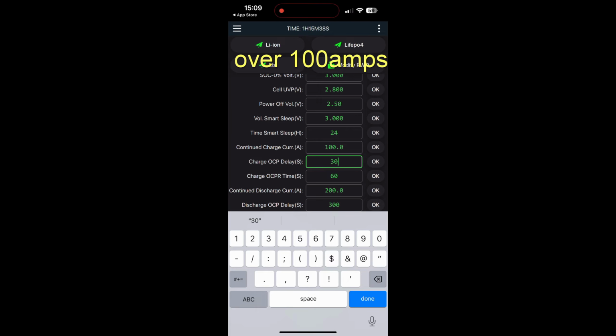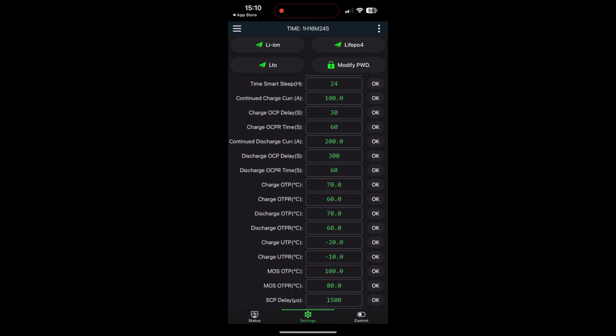Now, these BMSs that we have are a 200 amp BMS with a 350 amp peak. So it will sustain a 100 amp charging current for 30 seconds, and once it's reached 30 seconds, the BMS will disconnect. Now, the setting below that, charge over current protect reset, is how long the BMS will wait until it allows charge current to start coming back in. So let's say you've got that set to 100 amps. Once it hits, say, 101 amps, it'll sustain that for 30 seconds. Once it's gone over 30 seconds, it will disconnect for 60 seconds.